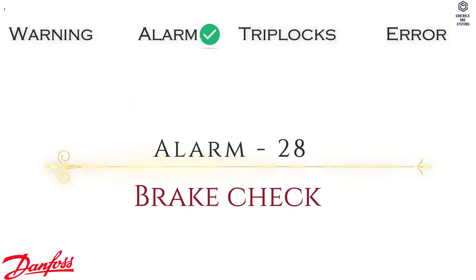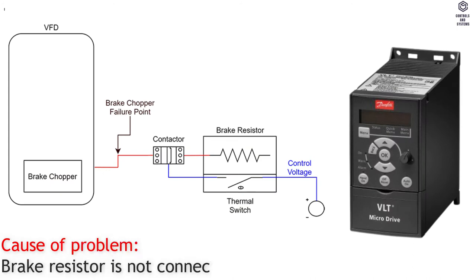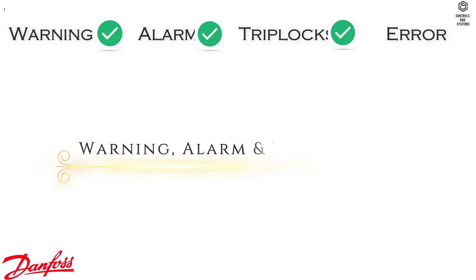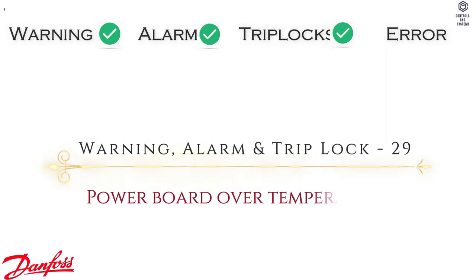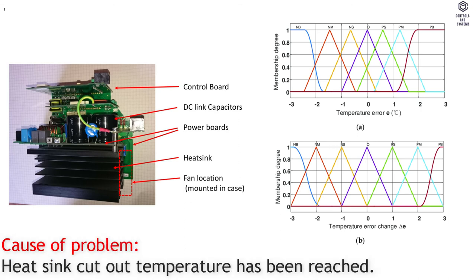Alarm 28: Brake Check. Cause of Problem — brake resistor is not connected or not working. Warning, Alarm and Trip Lock 29: Power Board Over Temperature. Cause of Problem — heat sink cut out temperature has been reached.